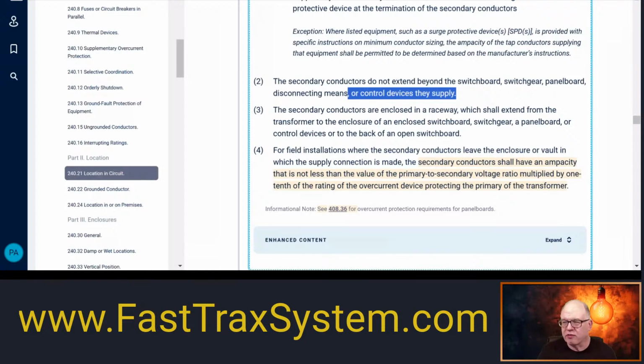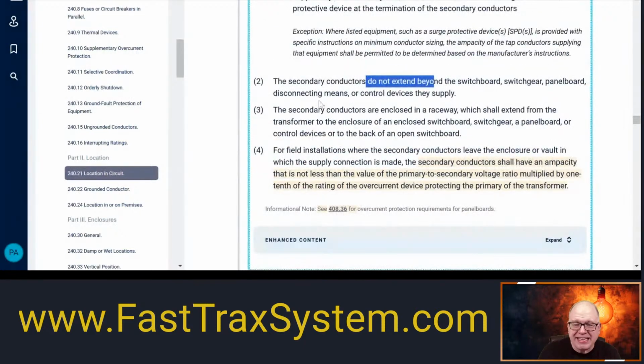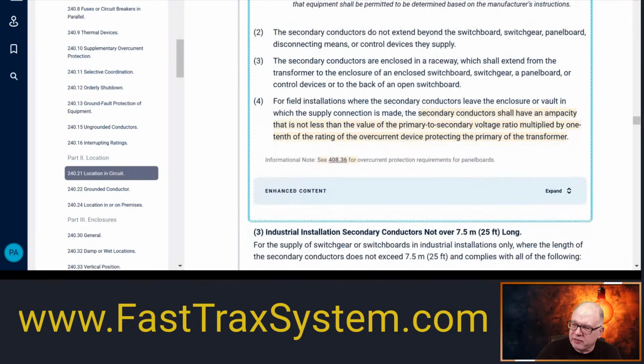That's it. So as long as it doesn't extend beyond that, then we're good to go. Next, that was probably pretty easy to do. You're just going straight from the transformer straight to the piece of equipment. In this case, our enclosure with our panel board in it, with the main breaker. All right, now, the next one is this one, secondary conductors.